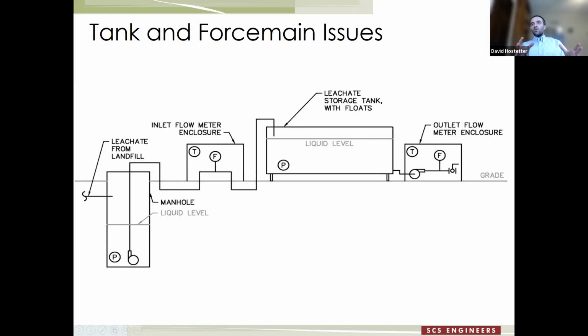There's a couple different things we did with this RMC system. We set it up so the initial use was that truckers would be able to log into the system to see what the liquid levels are, and know when they should come out to the facility to take liquids. We're also using it to monitor the amount of flow coming in and out of the tank.